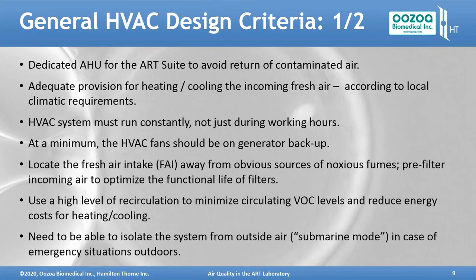In terms of general criteria for designing your HVAC system, it needs to be a dedicated air handling unit to avoid the return of contaminated air from other spaces. You've got to have adequate provision for heating and cooling of the incoming fresh air according to your local climatic requirements. If you're in Calgary in the middle of the winter, you need to warm it up substantially, perhaps by 60 degrees Celsius. And if you're in somewhere like Doha, you'll need to cool it down because it can get to 50 degrees outdoors.